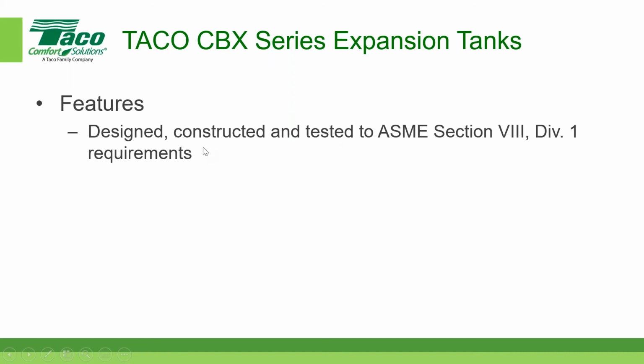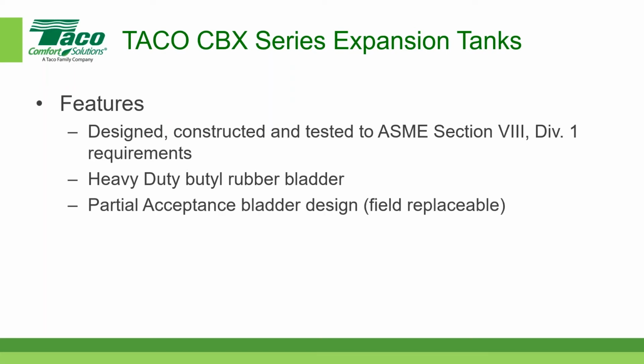But again, all of our expansion tanks, pressure vessels are made to that ASME code. I can't emphasize that enough, and I'm going to emphasize it every time I show you one of our expansion tanks. The same type of material, that bladder is the same type of material, that heavy butyl rubber. Partial acceptance, and again, field replaceable.